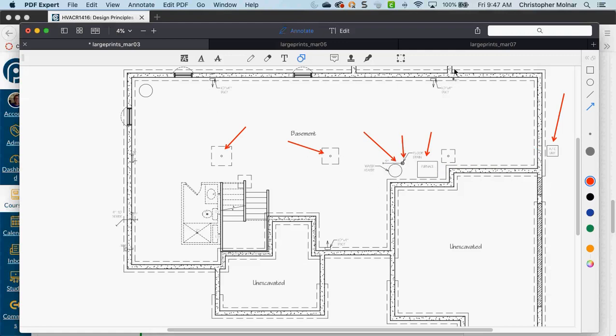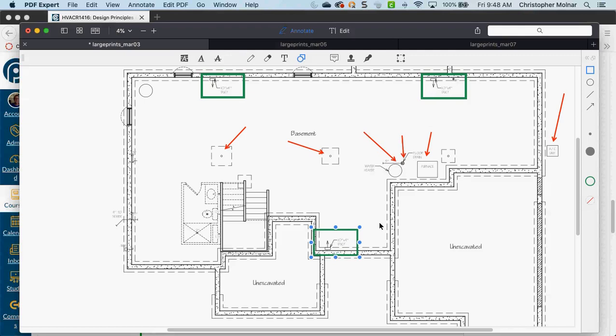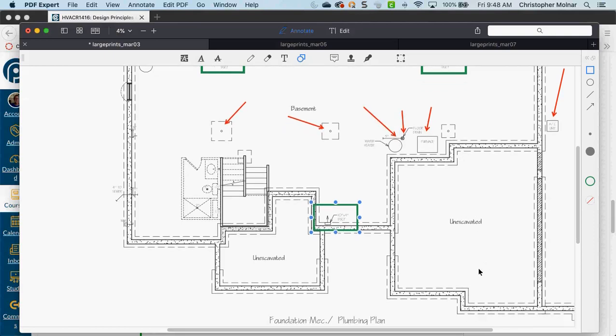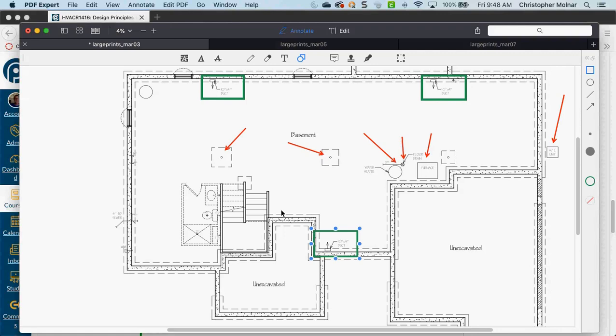On this basement plan I can see ductwork around the outside with direction-of-flow markings: a 10 by 4, another 10 by 4, and a 10 by 4. There's an unexcavated area on the side — probably a concrete pad for the garage — and another area that's probably a back porch concrete pad. All of this comes into play when we start looking at the air conditioning layout. Basements are important — we start from the bottom and work our way up when doing mechanical plans.